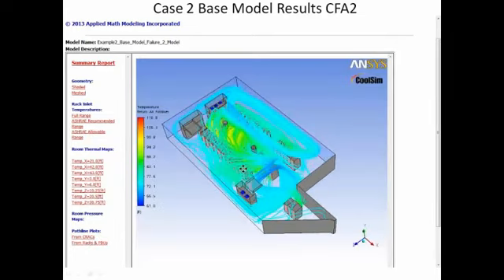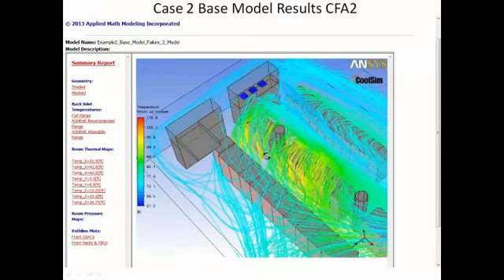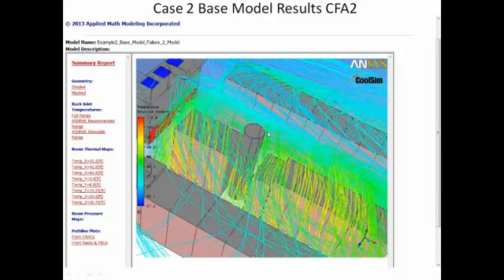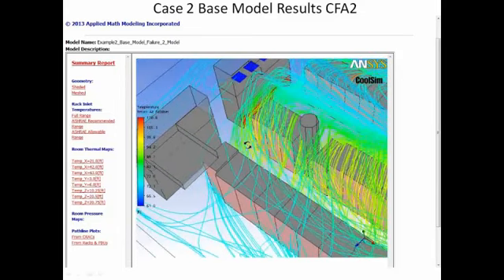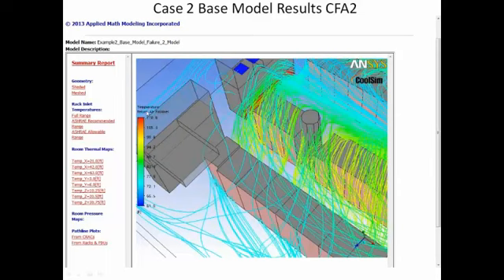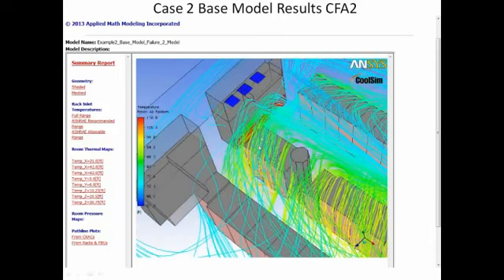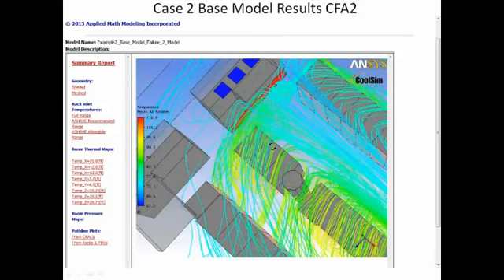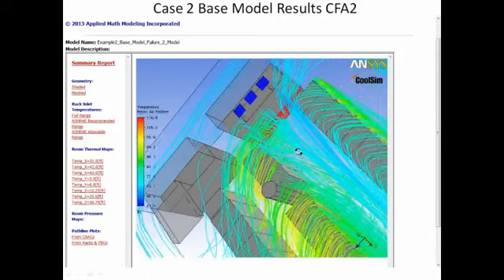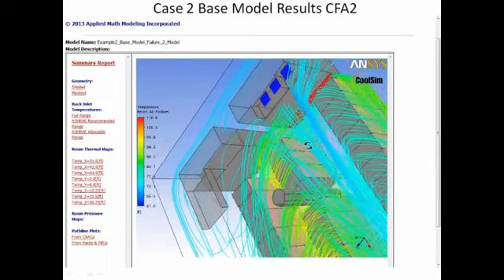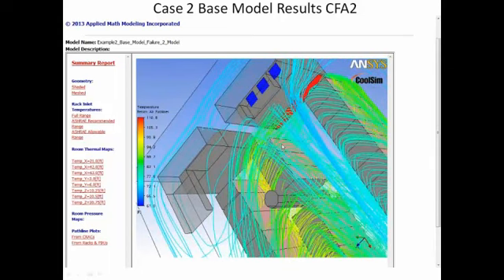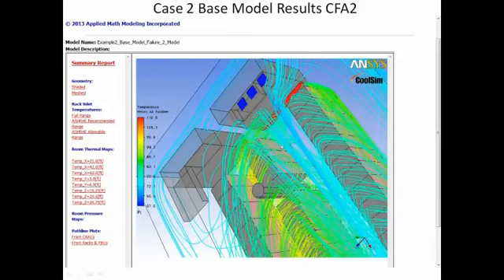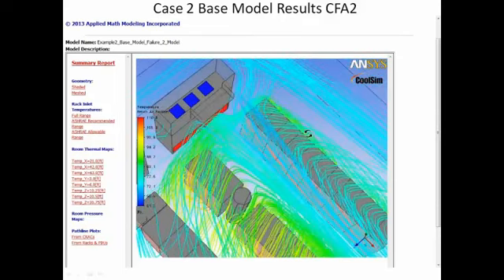Now, as it turns out, if we take a look here, Magnus, at the airflow, it becomes evident to us why this case is dangerous, why it is causing problems. You can see right here, this is the air coming back. We're looking here at air return. It says right here, temperature return. And the air is coming out of this hot aisle, and it's got nowhere to go. So it has to go up over the top and around this aisle and get sucked into that intake down low. And of course, during that process, it gets sucked into the intake of these racks and drives those rack temperatures up. So here, it's not so much supply problems as it is return problems.